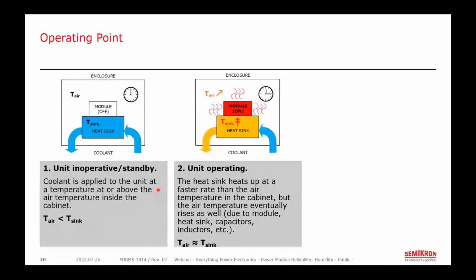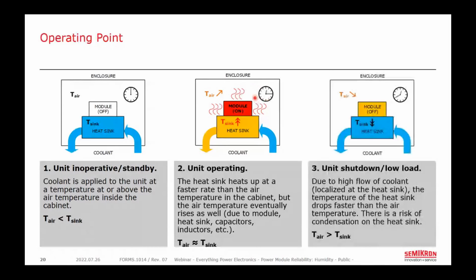When the power module begins switching, it generates losses and heats the heatsink as well as the coolant that is exiting the heatsink. After some time, the surrounding air inside the enclosure may warm up, as well as other components, pieces of metal and whatnot in here, due to heat within the converter. Other components, such as inductors and capacitors, may be heating this air as well. The risk of condensation occurs at the end, when there is a sudden change in load.